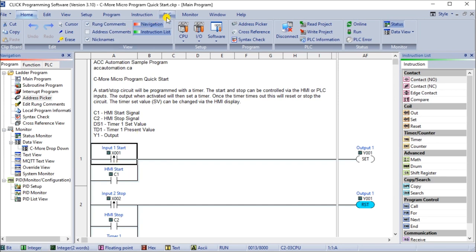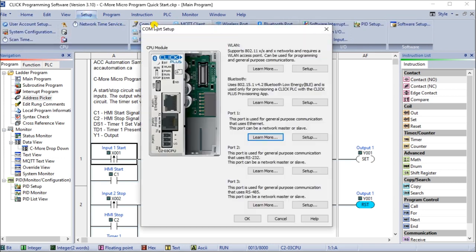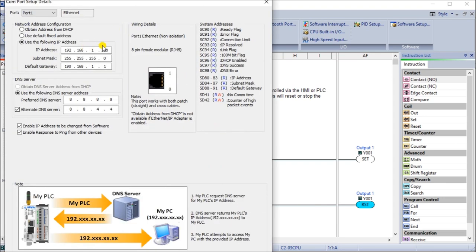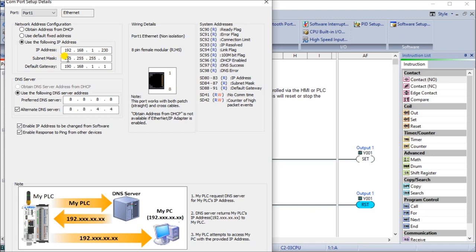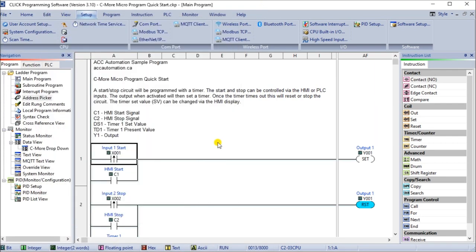Now the other thing we have to watch out for or look for on our PLC is we will actually go into our setup and then look at our COM port setting because we're going to be using our Ethernet port in order to communicate to this PLC. So we'll just hit setup on port number one, which is our Ethernet port. And you will see that we have it set for a static IP and we need a static IP in order to make sure that we have that same device there at that same time all the time. So we're using IP address of 192.168.1.230. We have a subnet mask, which must match everything else you're using in that network. And then we have a gateway that allows this unit to connect down to the internet, which we're not using right now, but we'll set it anyway. So we have to remember this 192.168.1.230. So we can close that down. So that is our PLC program. And we're all set to go.